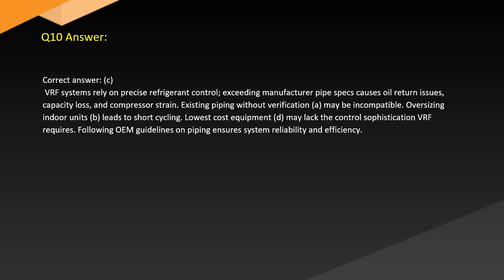Answer. Correct answer: C. VRF systems rely on precise refrigerant control. Exceeding manufacturer pipe specs causes oil return issues, capacity loss, and compressor strain. Existing piping without verification may be incompatible. Oversizing indoor units (B) leads to short cycling. Lowest cost equipment (D) may lack the control sophistication VRF requires. Following OEM guidelines on piping ensures system reliability and efficiency.